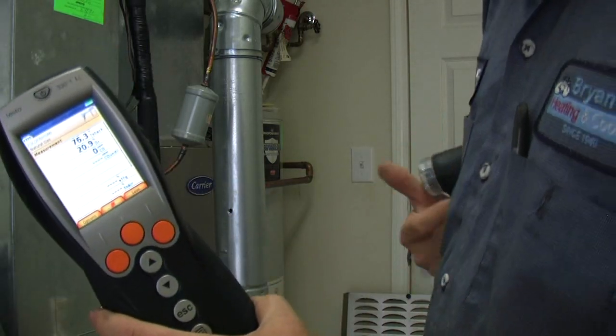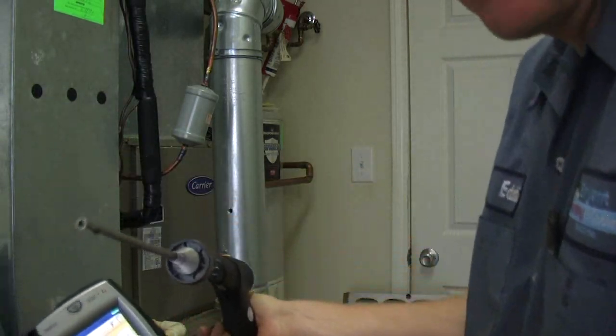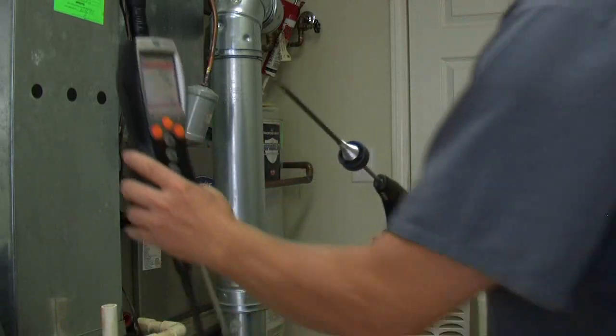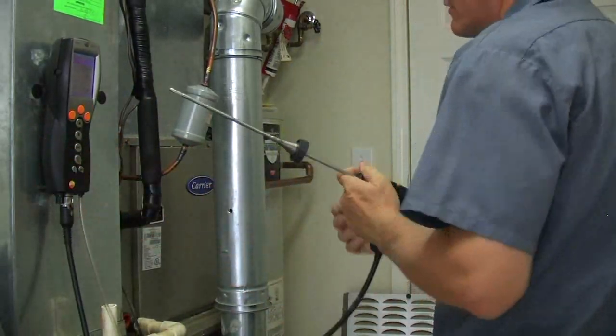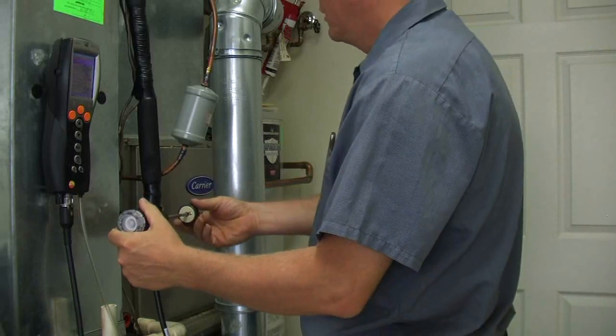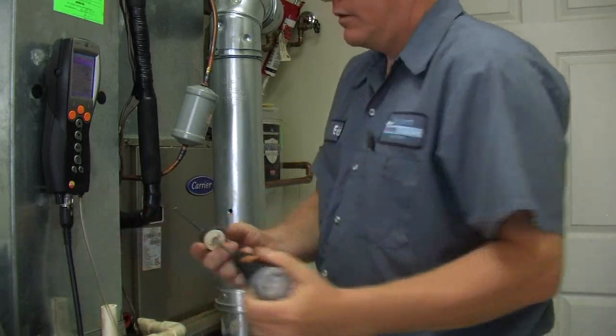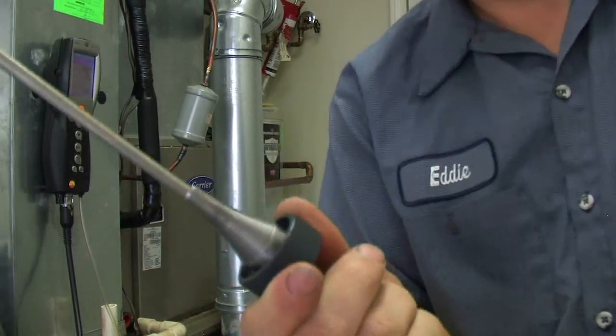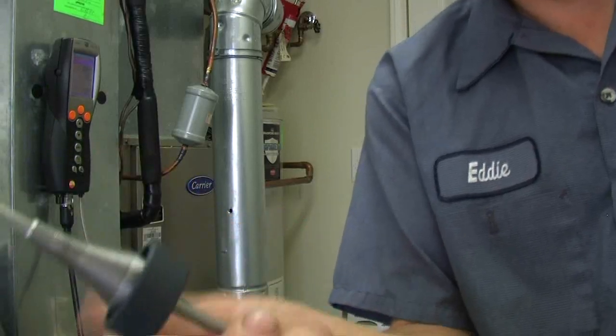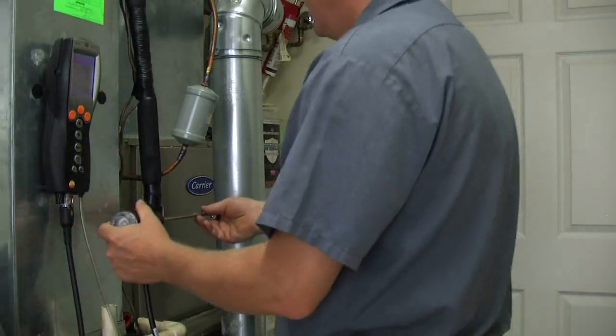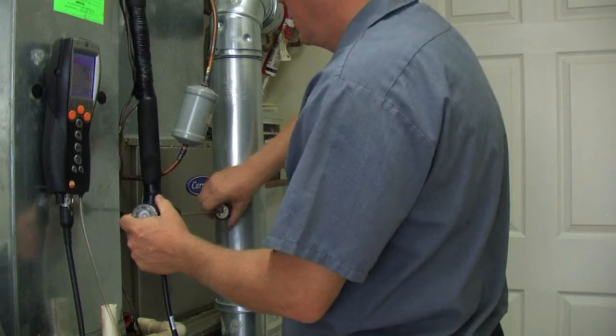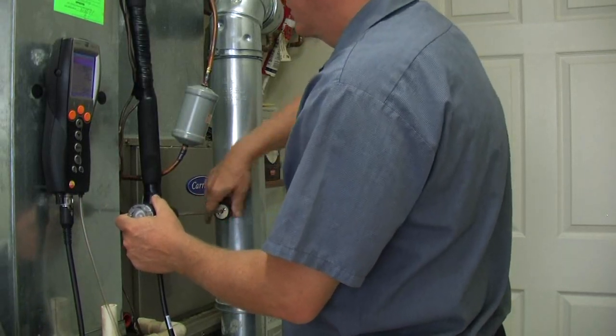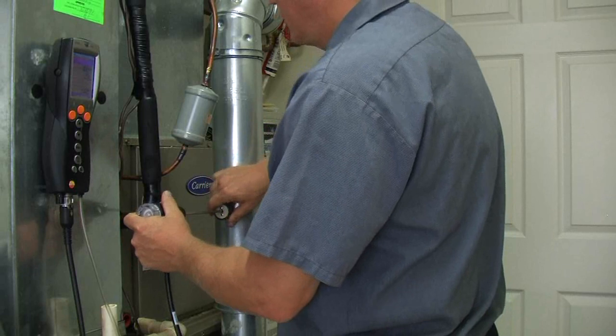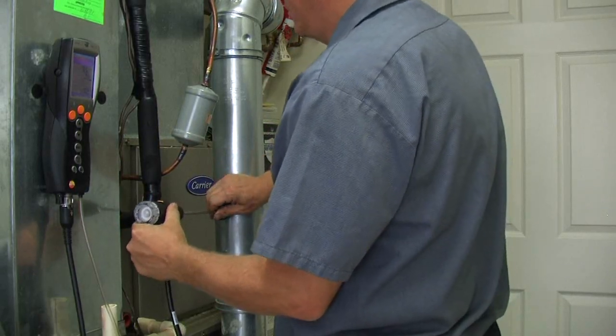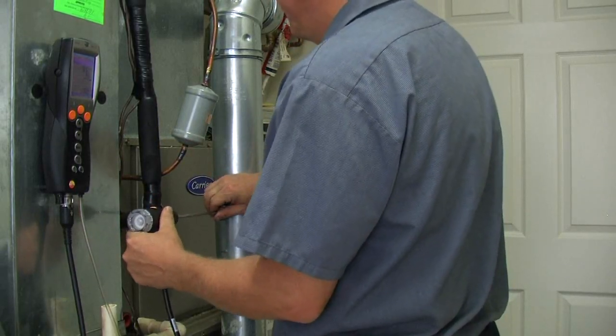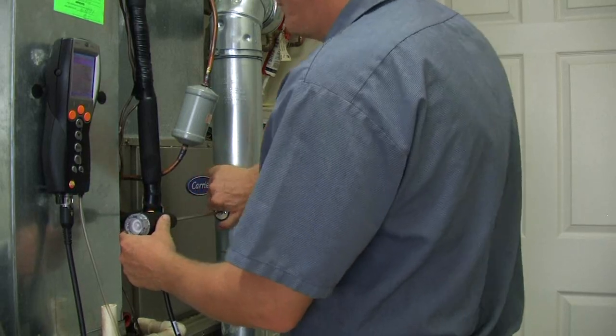It's going to start pumping air through the probe here. Mount that there. Go ahead and stick my probe. The probe you want to get, this particular one has this little fitting that you screw into the B-vent, so it holds it in place. So I just kind of screw it in there. Now I usually push mine all the way against the other side and kind of pull it out to where it's going to be in about the middle. About right there.